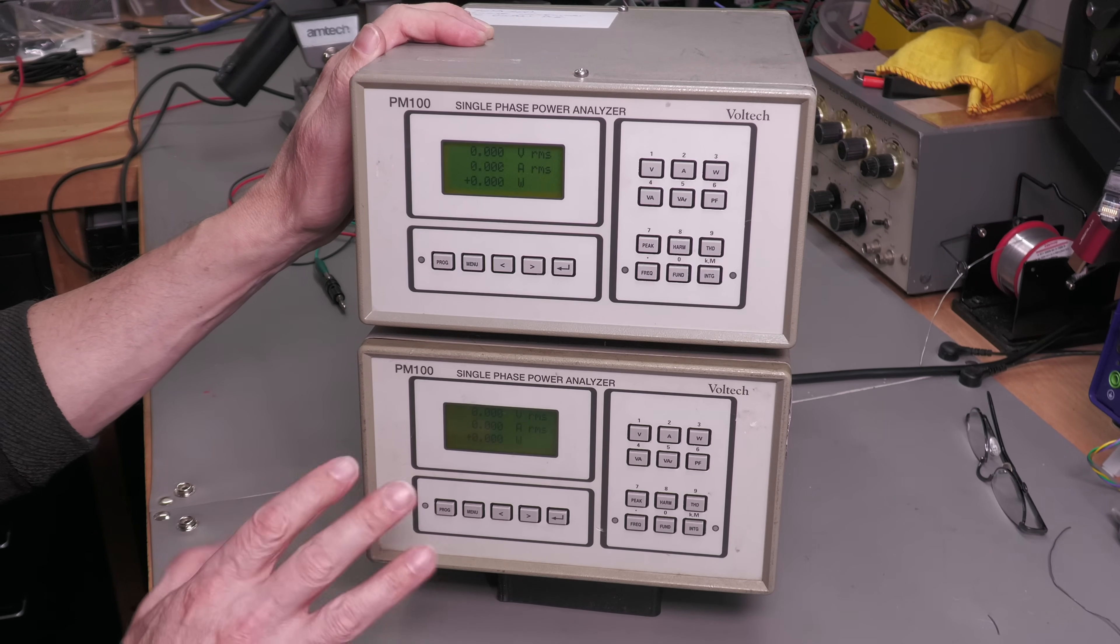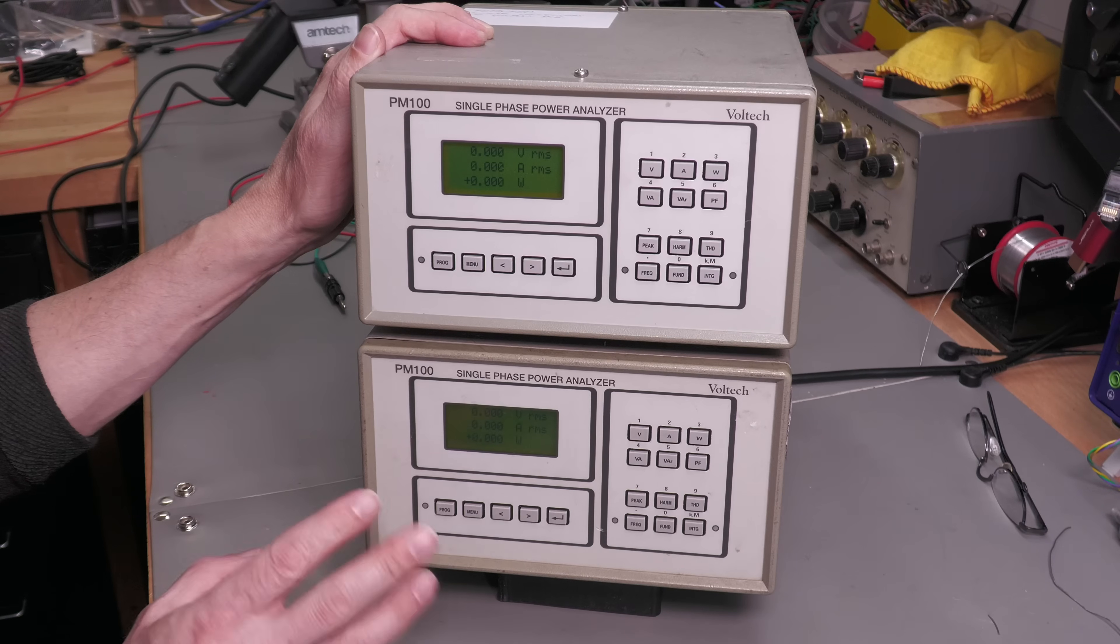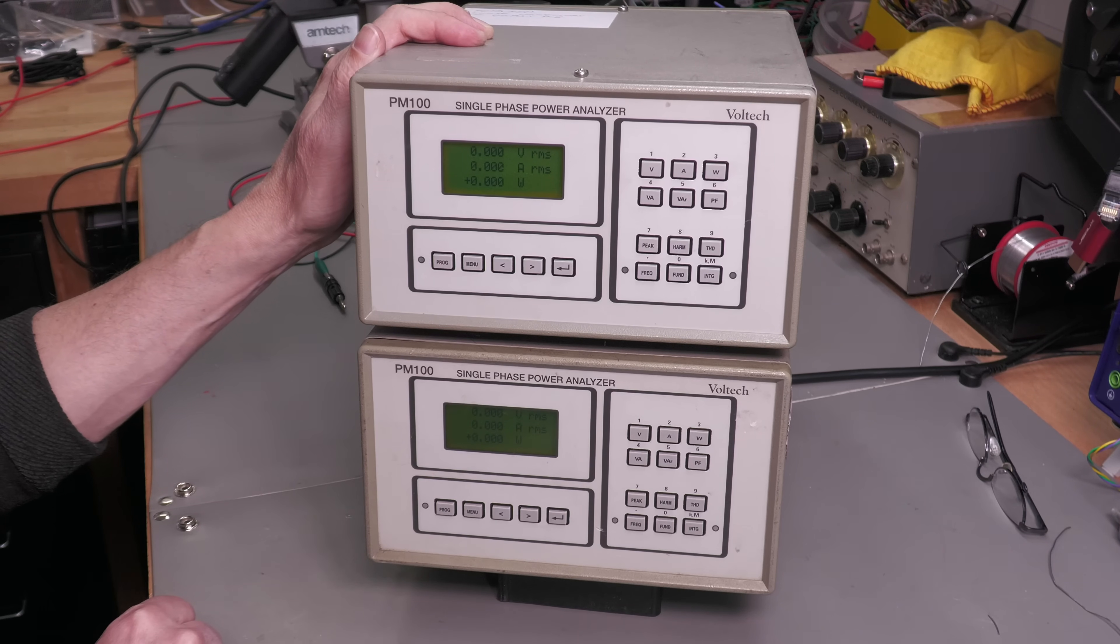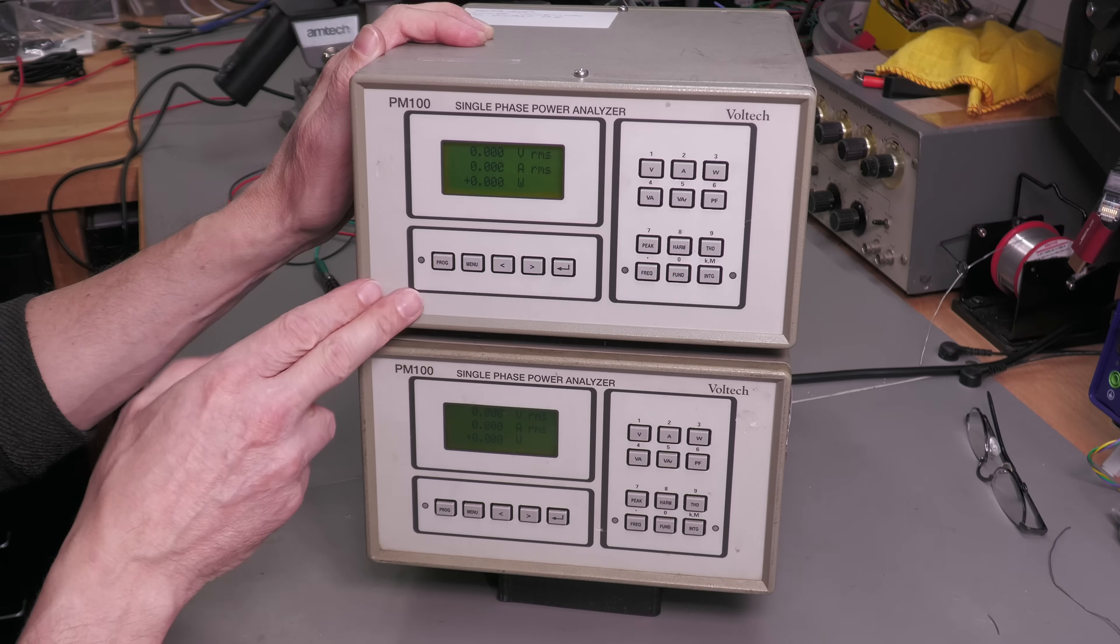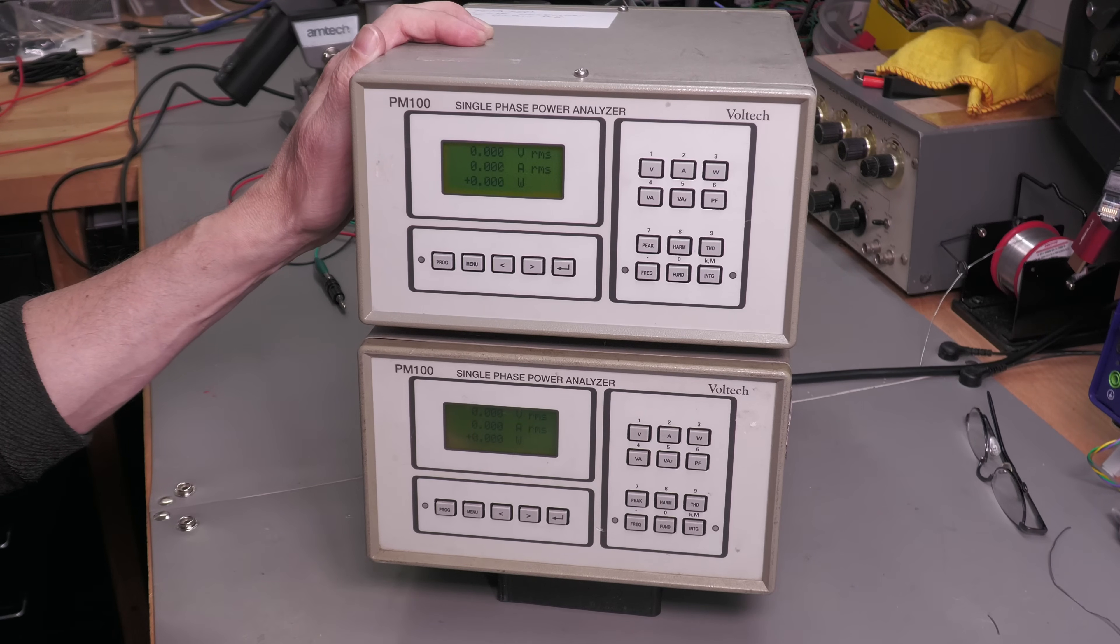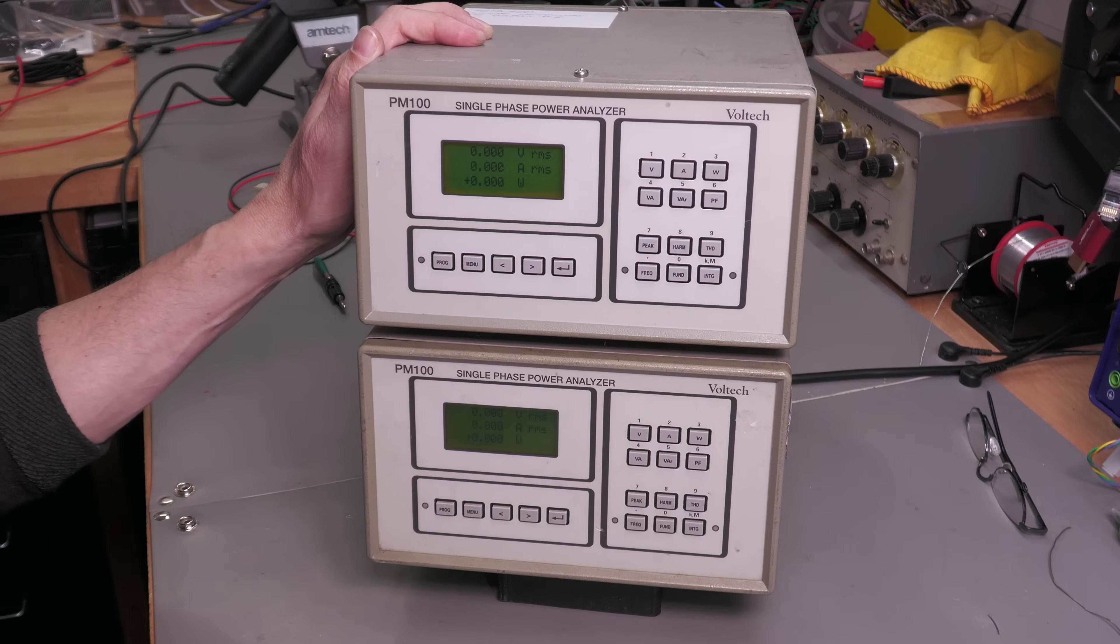But the big question is, especially with the first unit with those two ribbon cables that were loose in their sockets, was that really a fault? Did they jump out on their own? And the jury's out on that one. Because sometimes when companies want to upgrade their test equipment in their workshop, they might sabotage their equipment so that they can get it through management to go and buy some new ones. Well, who knows. The second unit with that IC that wasn't fully soldered in, was that the problem? Possibly, although the solder joints did look okay, albeit they were on the limit there. So maybe that was the fault with that one.